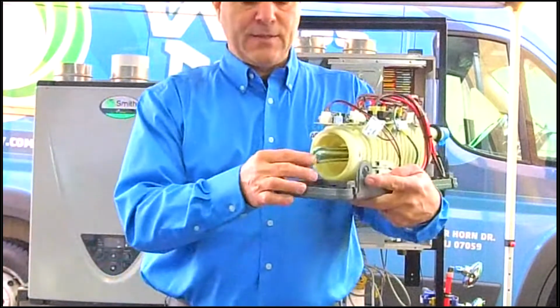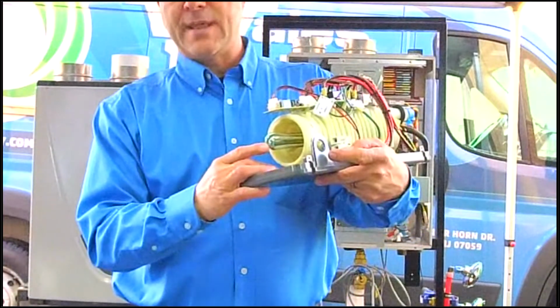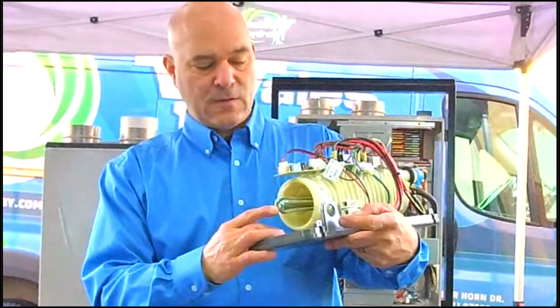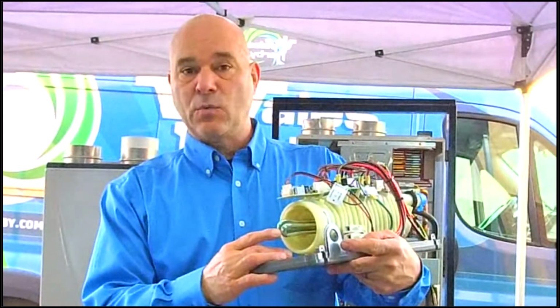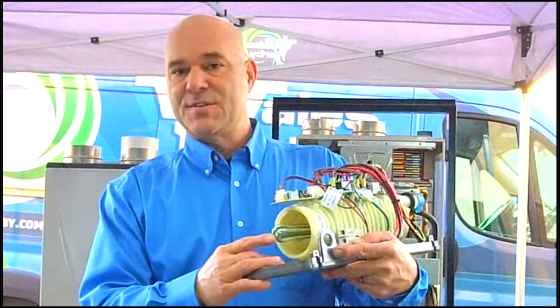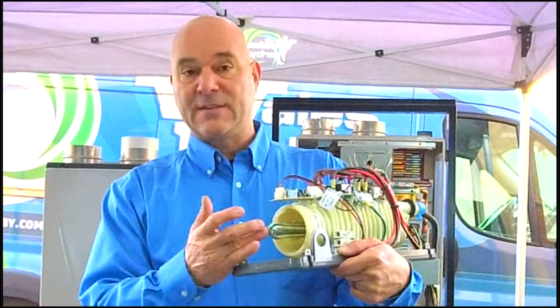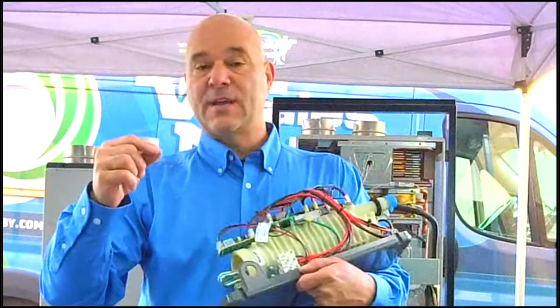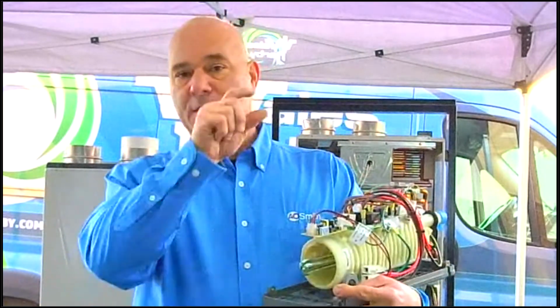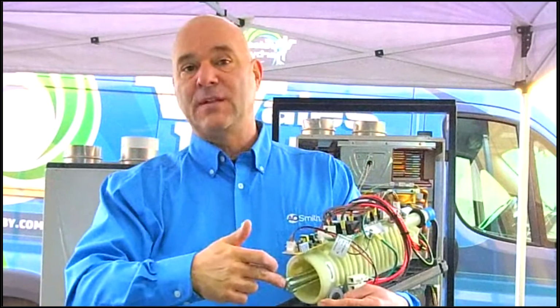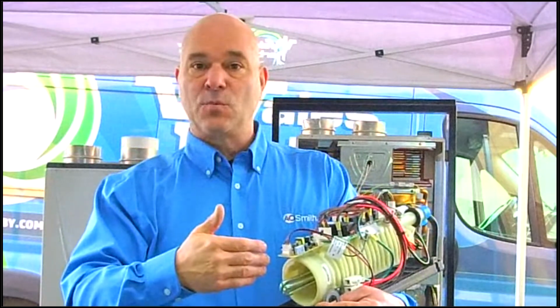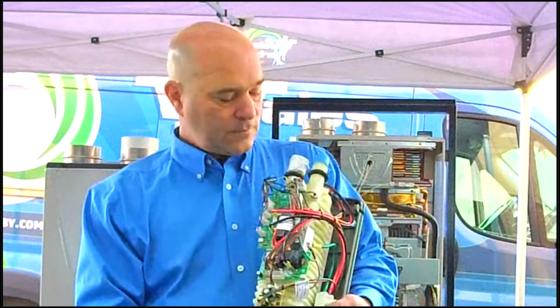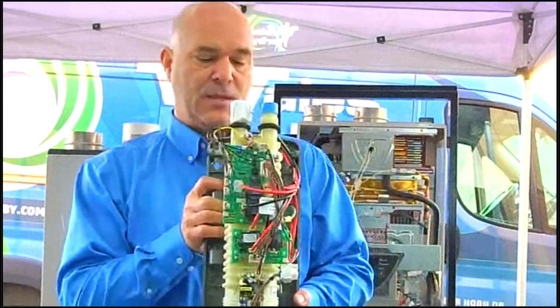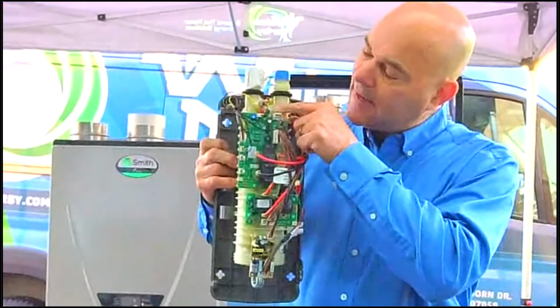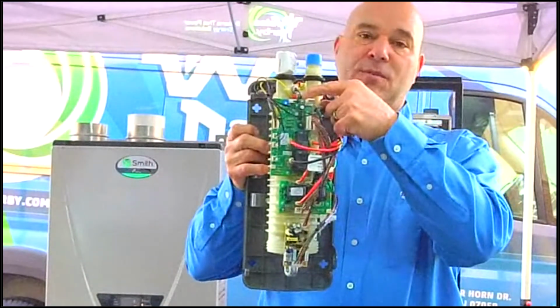And this is different in the electric tankless world. We use a standard style element. So if you're used to doing electric water heaters, tank style water heaters, we use the same style. Majority of the manufacturers out there use basically, if you ever worked on an appliance dryer and you've got the springs that go around for the electric heat, that's what most manufacturers use in electric tank style or electric tankless water heaters.